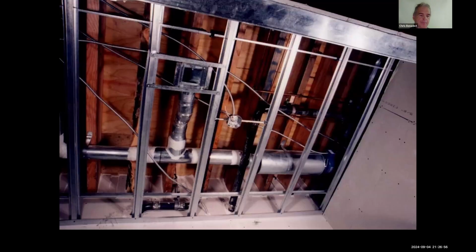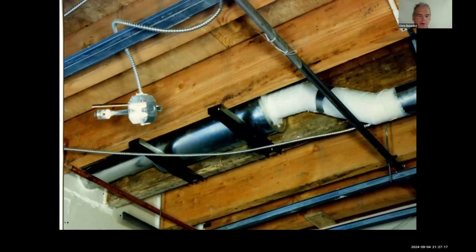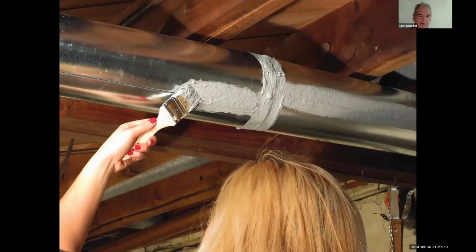Here's some exhaust-only ventilation. The big thing, the fat piece of pipe on the right, that's a muffler. So people don't hear the noise from the fan. Fans have gotten quieter, but you still might want a muffler. And the box where the duct terminates, that's where the grill goes. And we put an air regulator in there. There's a close-up of a muffler. Here's the goop going on the duct to air seal it, both the circumferential and longitudinal seams.